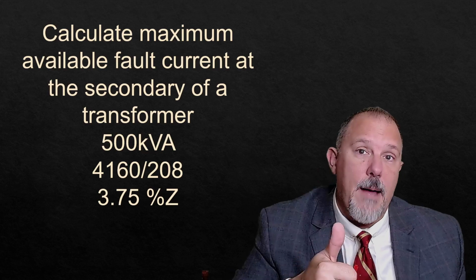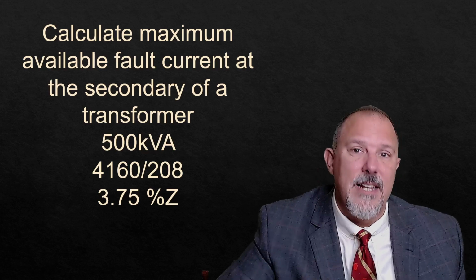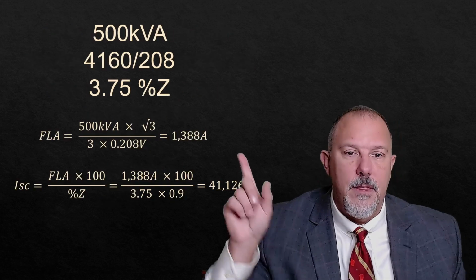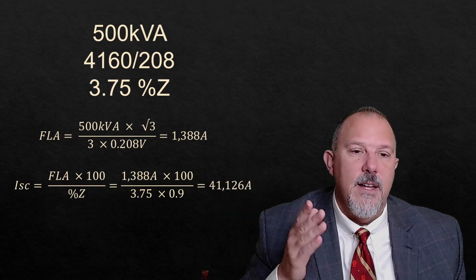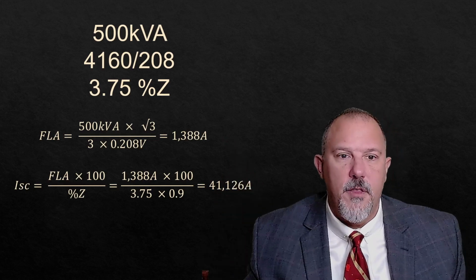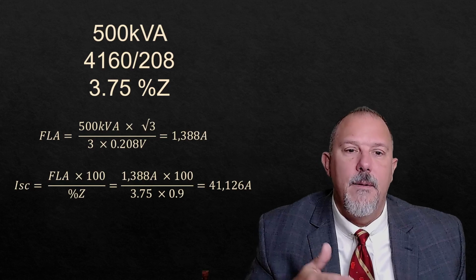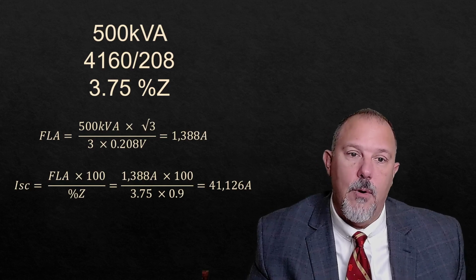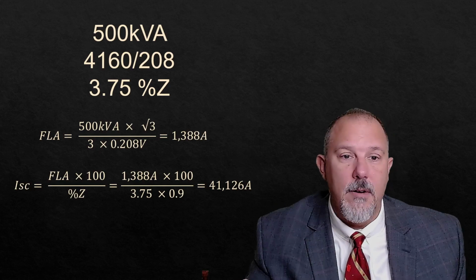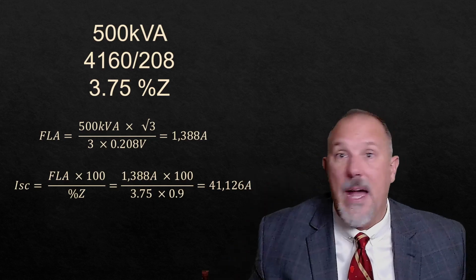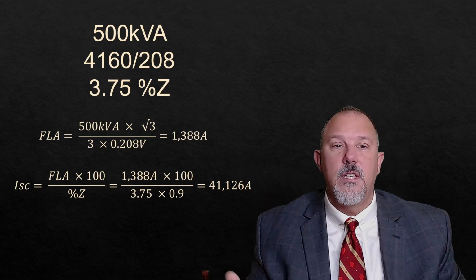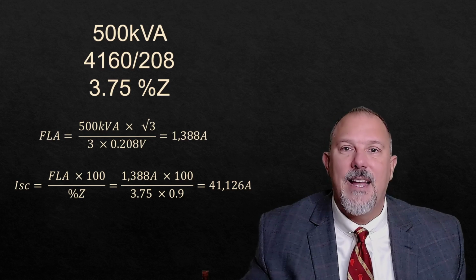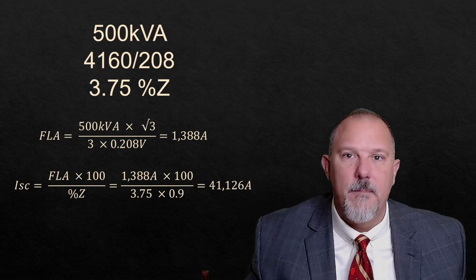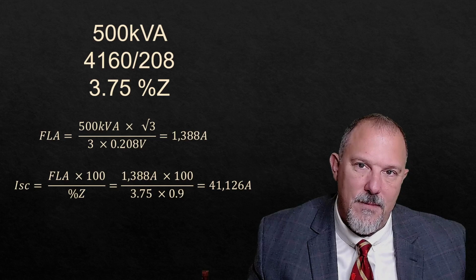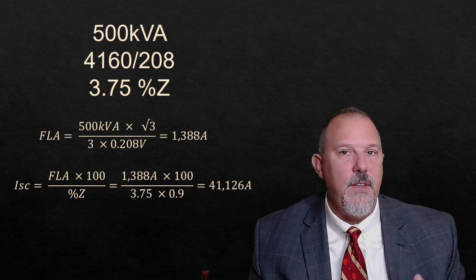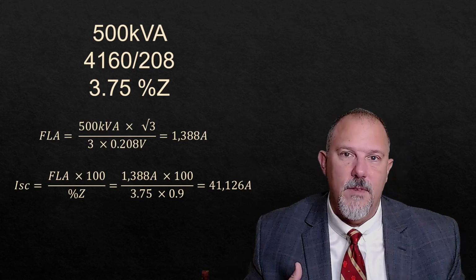So the first step is to calculate full load amps on the secondary of this transformer. How do I do that? That equation right there: kVA times the square root of 3 divided by 3 divided by the kV, 0.208. If I used 208, I've got to multiply the top by 1,000. You may have seen this equation as the kVA times 1,000 divided by the square root of 3 divided by the voltage. It's just playing with the kVs versus volts, the thousands.